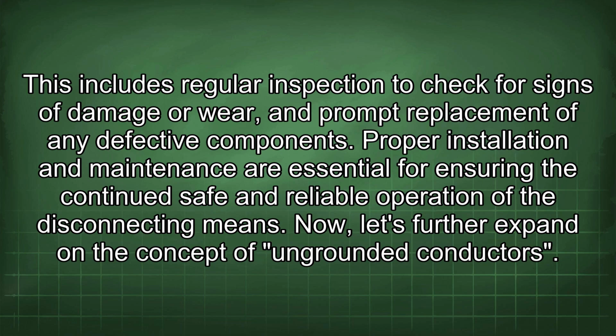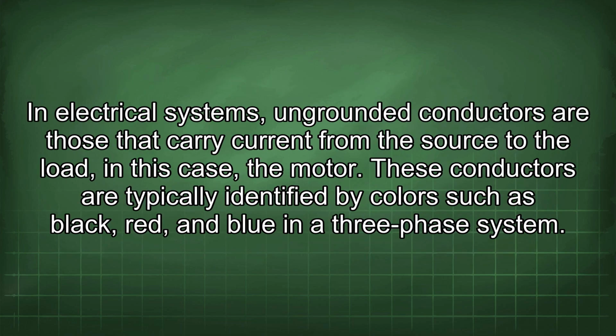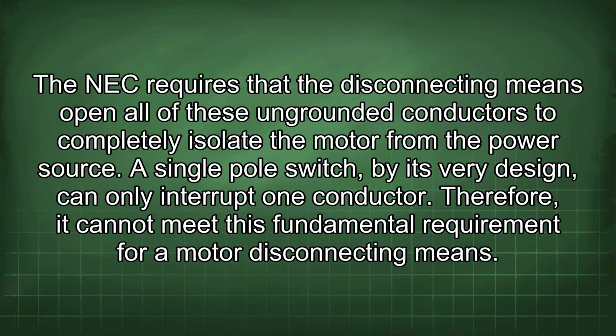Now, let's further expand on the concept of ungrounded conductors. In electrical systems, ungrounded conductors are those that carry current from the source to the load, in this case, the motor. These conductors are typically identified by colors such as black, red, and blue in a three-phase system.